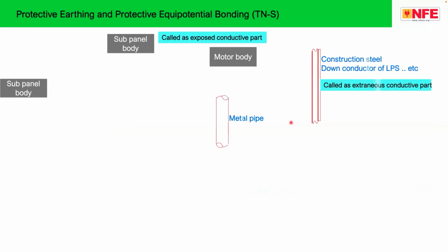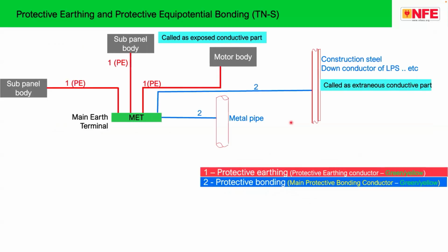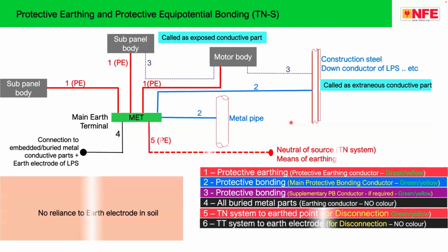One subject which is extremely important in medical locations in hospitals is earthing. By looking at the word earthing, generally biomedical engineers and electrical engineers, or normally the experts, think that earth means soil. So people try to make earth in the soil, which is absolutely wrong. Here you can see sub panel, motor, these are exposed conductive parts. Then your building has got extraneous conductive parts. Connecting all the dead metal parts in your building to a common bus bar in a typical fashion is earthing.